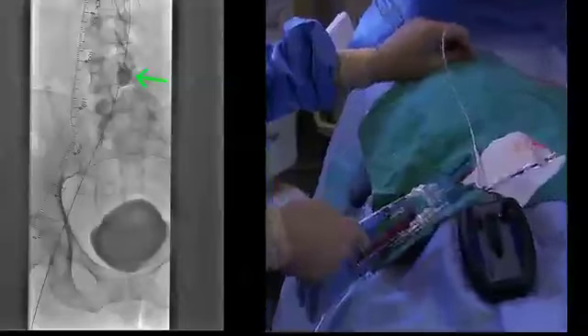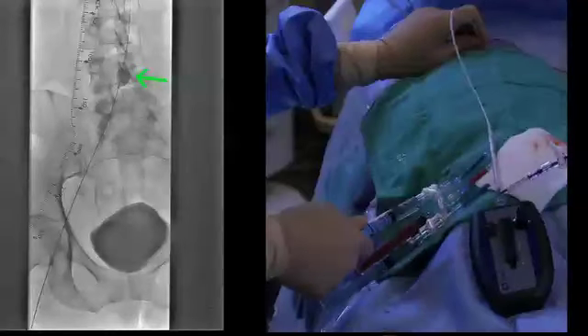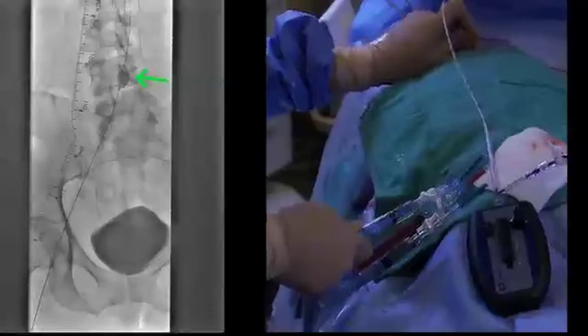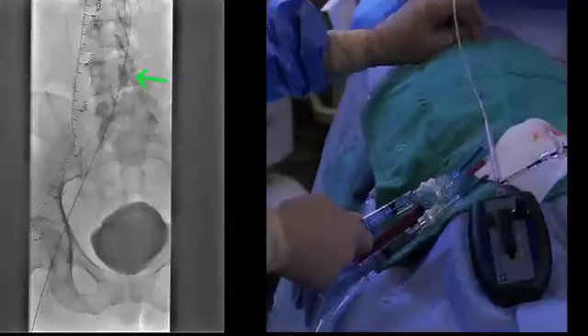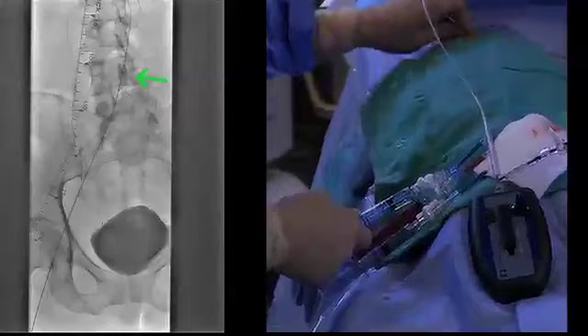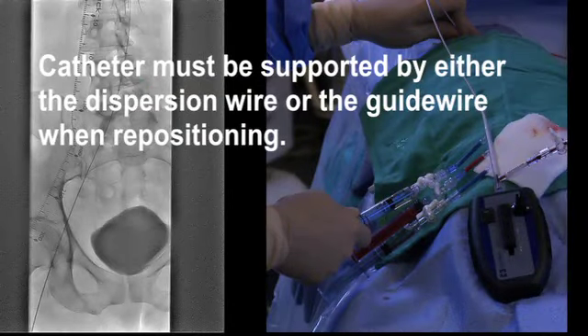When the Trellis system is being used with the antegrade approach, partially or completely deflate the distal balloon and, under fluoroscopy, reposition the device. Watch for any change in balloon shape indicating an obstruction that may require adjustment of the balloon inflation volume. The catheter must be supported by either the dispersion wire or the guide wire when repositioning. When the Trellis system is being used with a retrograde approach, completely deflate both balloons and, under fluoroscopy, reposition the device. Once the catheter is repositioned in the next location, inflate the balloons and repeat the treatment procedure.